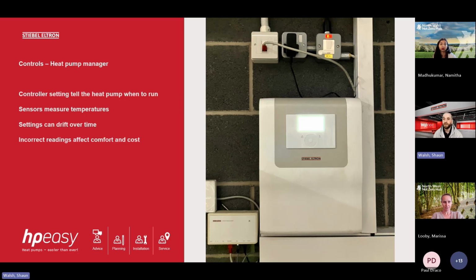Controller settings, again, is important. During initial commissioning, it will be set up to run as efficiently as it can be. But over time, you'll find end users will alter those settings if there's a change of property owner and they like it a bit warmer than the previous owner, or vice versa. They might come in and try and adjust some settings, and they might not adjust all of the settings correctly. So it's important that you take your original commissioning documents with you when you go to site and check that the parameters that are in there match the original commissioning and the original design of how it was intended to be used.